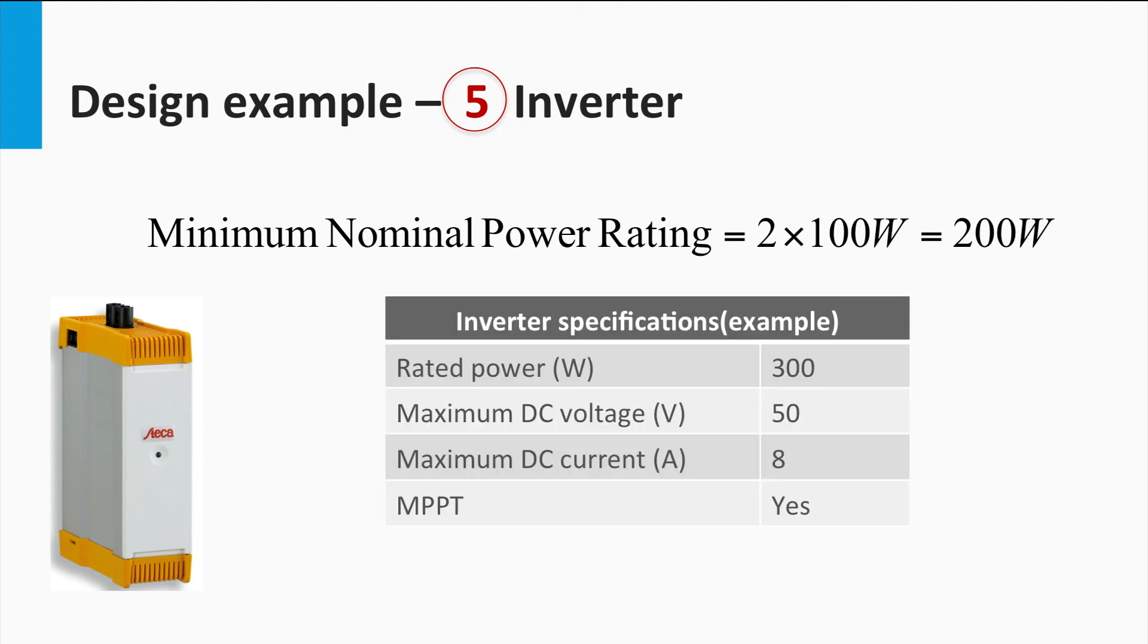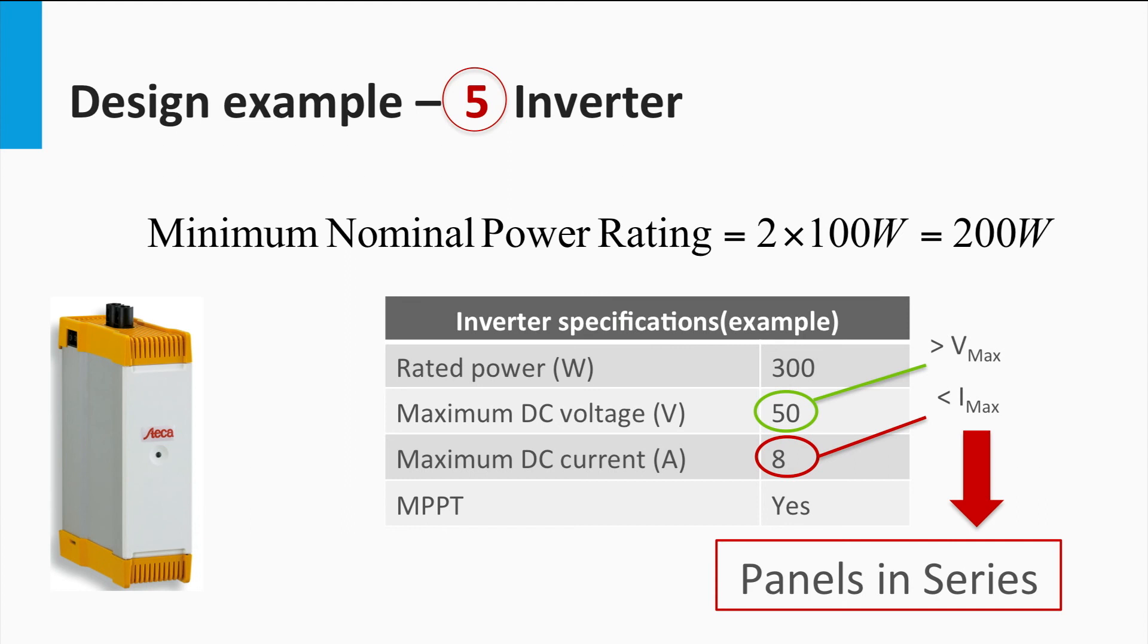Let us look at the operational parameters of an example inverter that fits the bill with respect to the required minimum power rating. Note that this inverter has a maximum power point tracking feature, thereby making the panels work at maximum power point. Looking at the IV ratings of the DC side of the inverter, we see that the maximum DC input voltage for the inverter is greater than the maximum voltage.